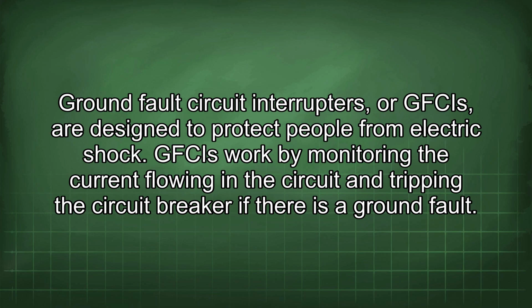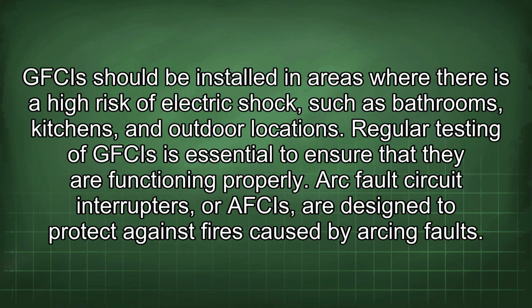Ground fault circuit interrupters, or GFCIs, are designed to protect people from electric shock. GFCIs work by monitoring the current flowing in the circuit and tripping the circuit breaker if there is a ground fault. GFCIs should be installed in areas where there is a high risk of electric shock, such as bathrooms, kitchens, and outdoor locations. Regular testing of GFCIs is essential to ensure that they are functioning properly.